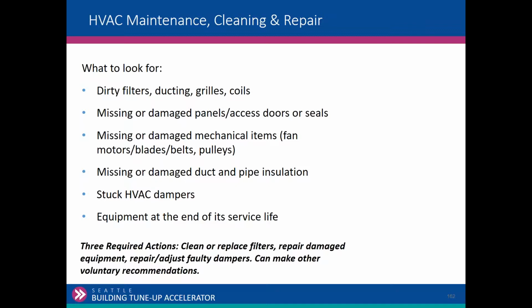Damaged duct or pipe insulation. So somebody had to remove some pipe insulation to do some work, never re-insulated the pipe. HVAC dampers that are frozen. Equipment at the end of its service life. And that's just getting the owner to think about, I've got some capital improvements I need to think about here. So, you know, just some general recommendations on cleaning and replacing damaged equipment, voluntary recommendations.